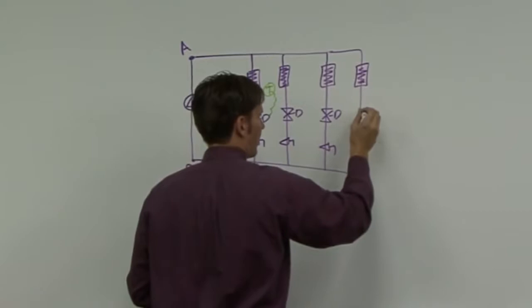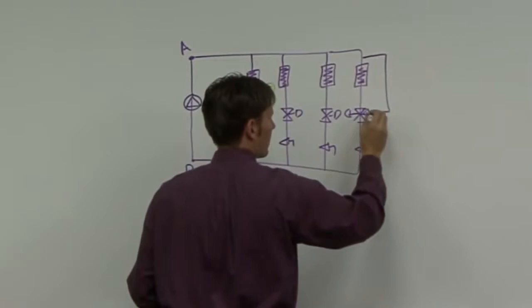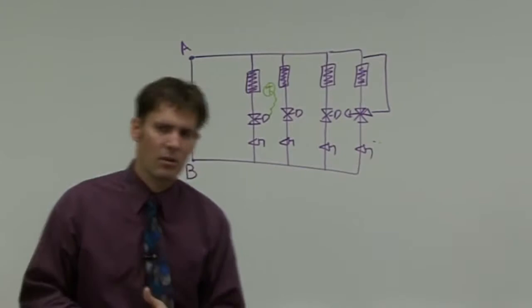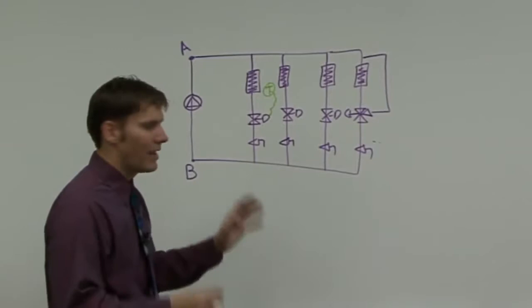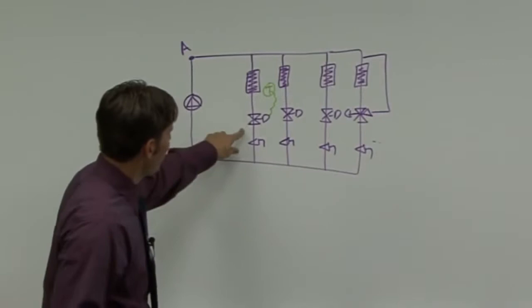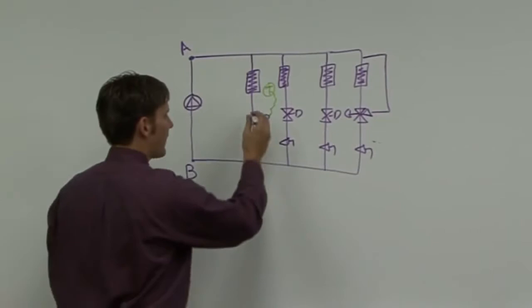Typically in these systems we'll see two-way control valves, though we might have a three-way control valve at the end of the loop. This is what we call a variable volume system. I have people argue with me that the volume never changes because the water fills the system. That's not the volume I'm talking about — I'm talking about the flow rate. The volume flow rate through the system will always change.